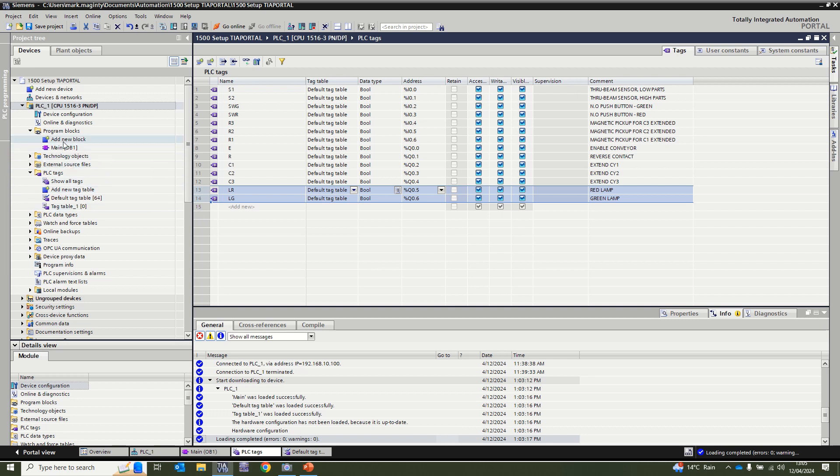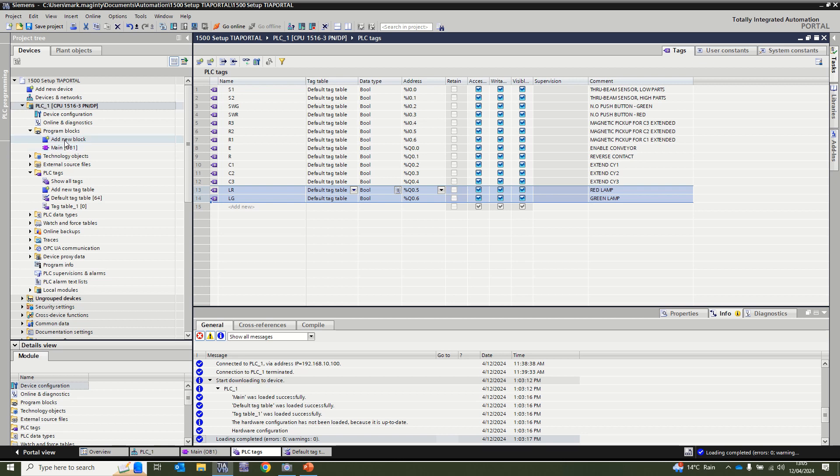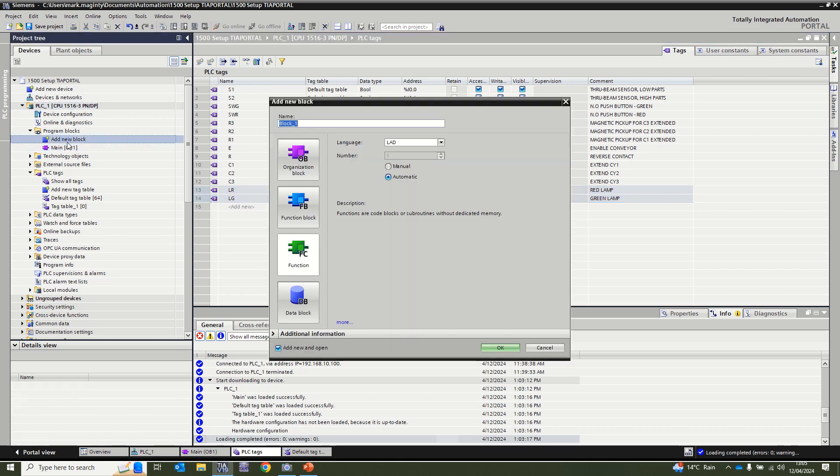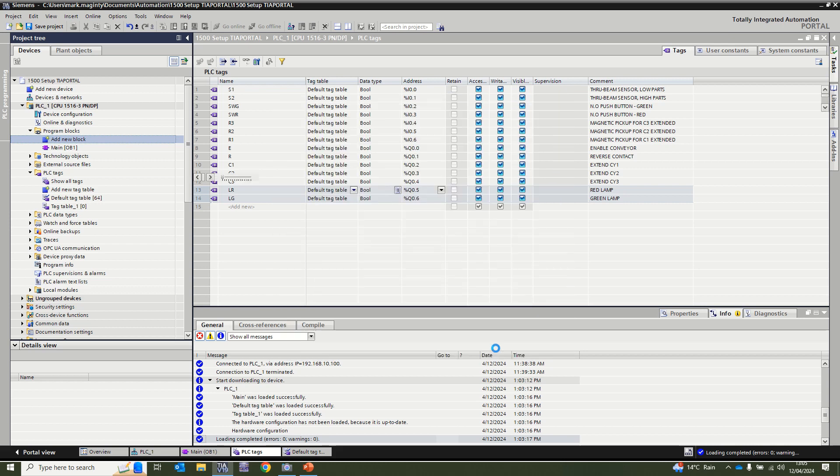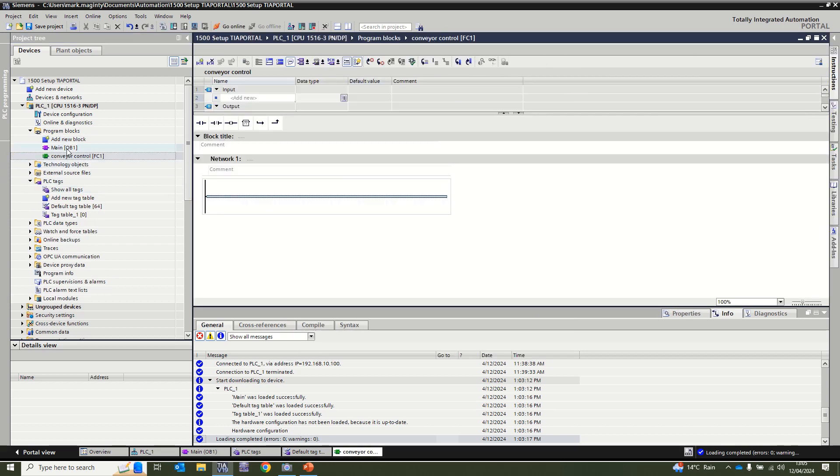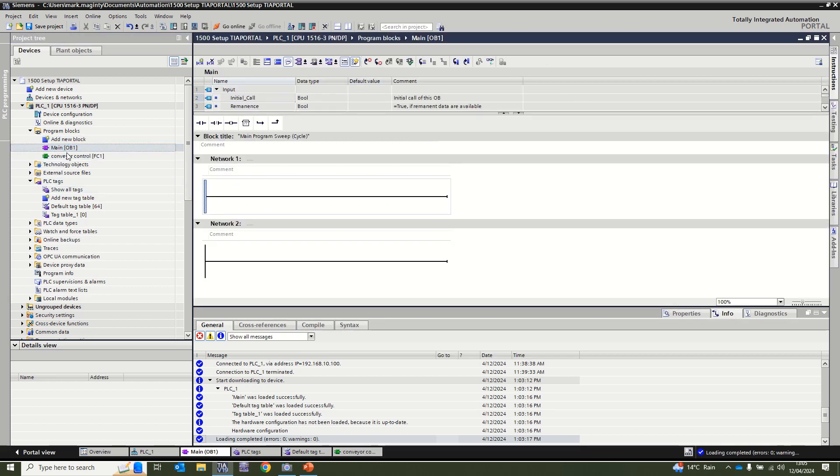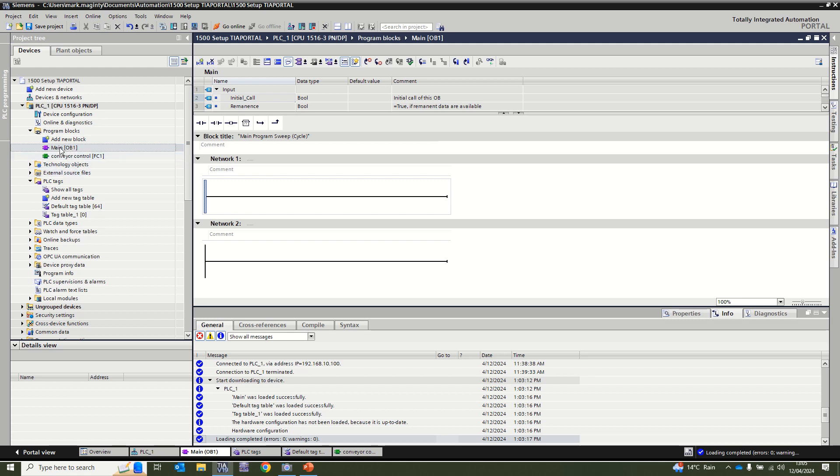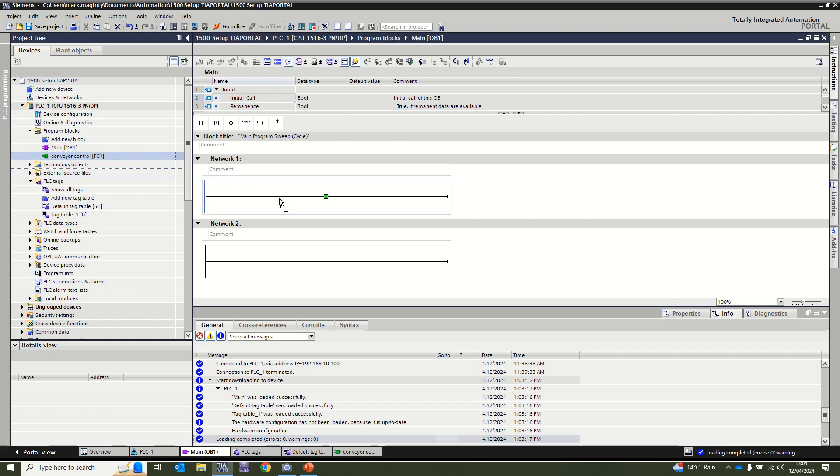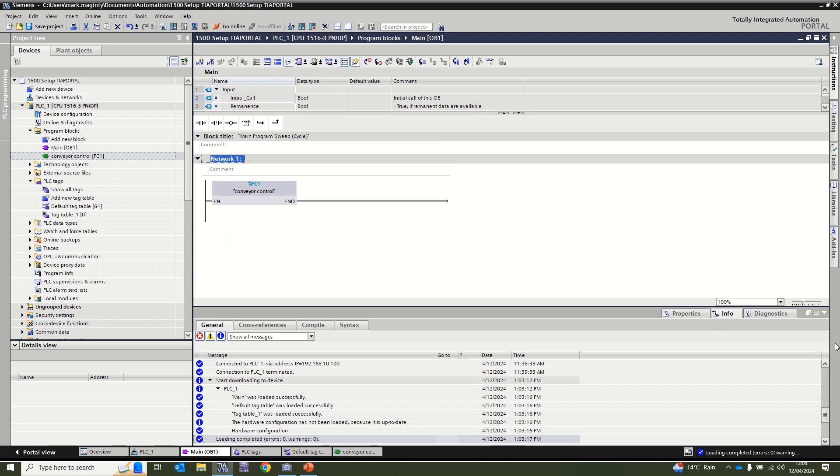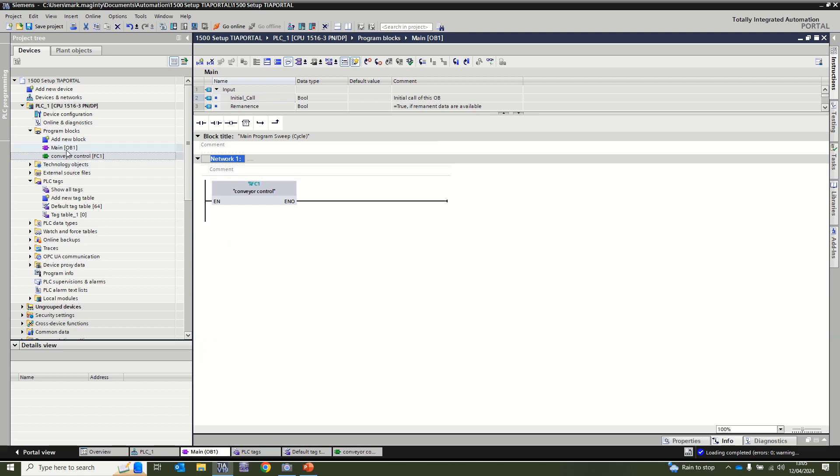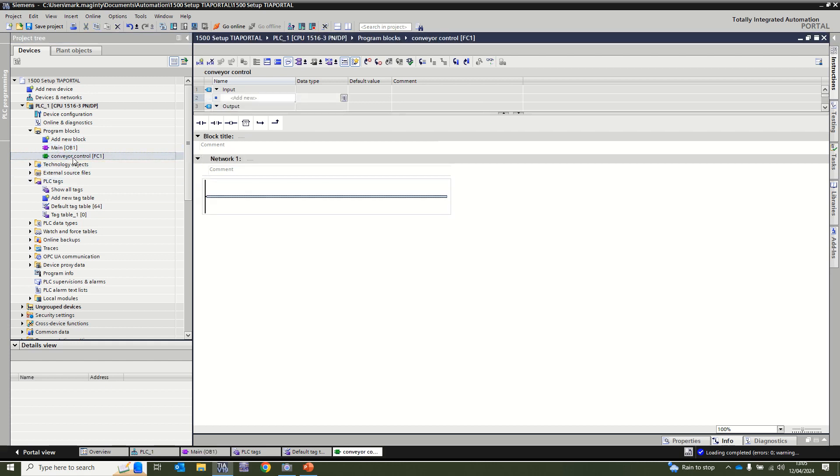We are going to program to make something very simple happen. First of all we need to go and add in a new block, so we go over here to function. I'm just going to call it conveyor control or anything similar. It's a good point of reference at this point to directly just call FC1 from OB1. When your machine powers up the only thing that operates is OB1, so you have to tell FC1 to operate which we have now done. Just for the sake of tidiness we'll put that in, and then under OB1 this is what we have. Conveyor control, which is an FC, which is a function, currently completely empty.